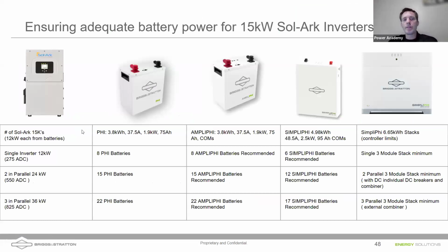Keep in mind that you need to have enough battery power to install the inverter. You don't want to install a 15K inverter with just a single battery stack like you can see there. A battery with communications will limit the amount of power the inverter is able to output. But if you have a non-communicating battery, like the Phi battery here on the left, you'll want to make sure that you have a big enough battery bank that at the rated continuous output power of the battery, it can match the inverter's drawn power. Each of these batteries gives 1.9 kilowatts of power output.